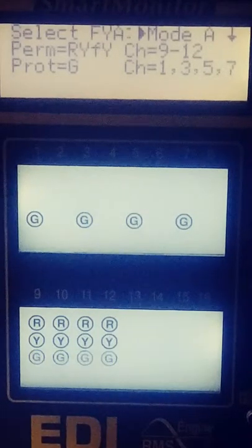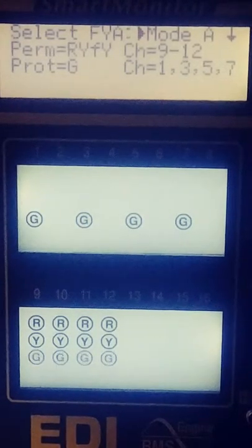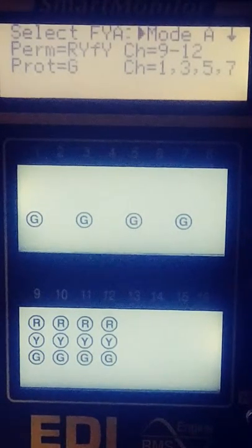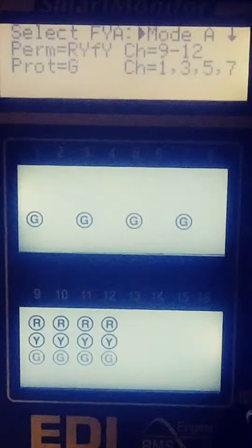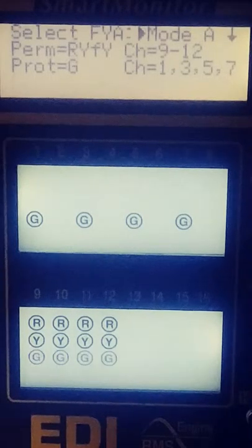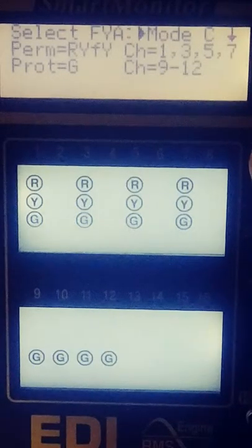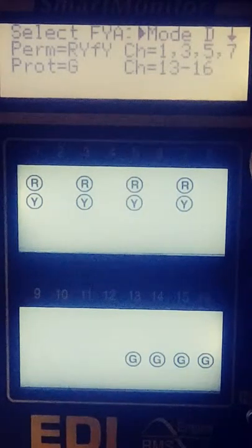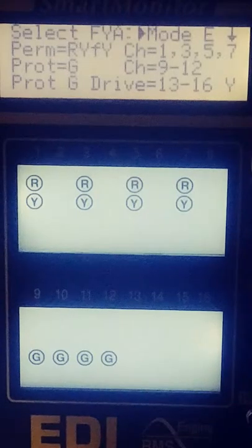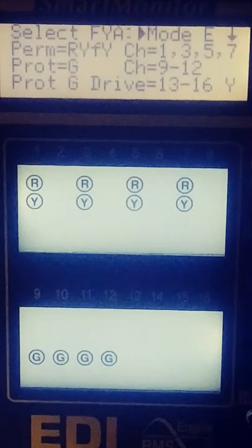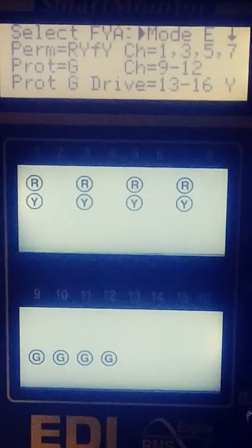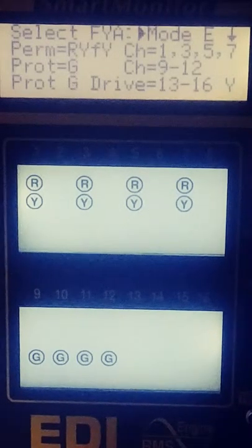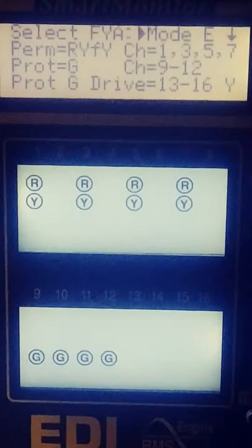On selecting the flashing yellow arrow mode you want to scroll until you hit mode E. Mode E is the mode that conforms to the way we wire and program the flashing yellow arrow in our TS2 cabinets.